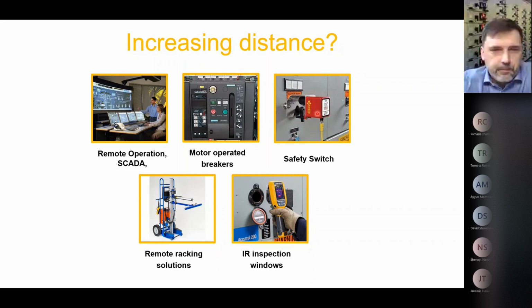Safety switch is a very nice feature, to be honest. If you would have to manually switch something, or electronically, I think part of it will now also be that you might switch things via Wi-Fi or Bluetooth, which is a very interesting feature because we have all the hardware with us as a smartphone. Remote racking solution. If you have a lot of ACB breakers, air circuit breakers, and you have to rack them in and rack them out, which means we have to physically put it inside the live place where it belongs, sometimes it's good to have a remote racking solution. So some kind of device like this will be remotely racking in, and we are just standing a few meters away.